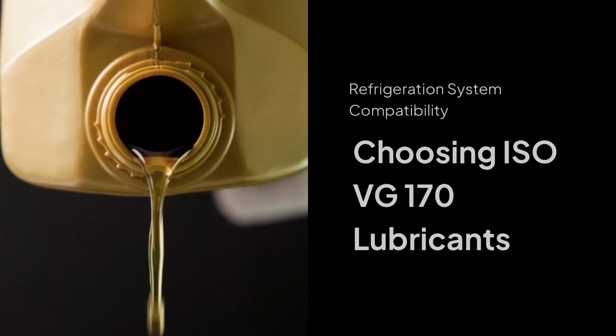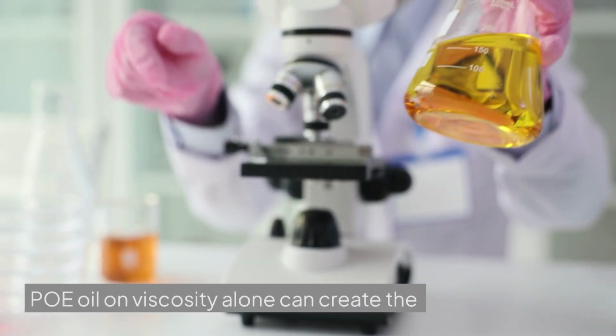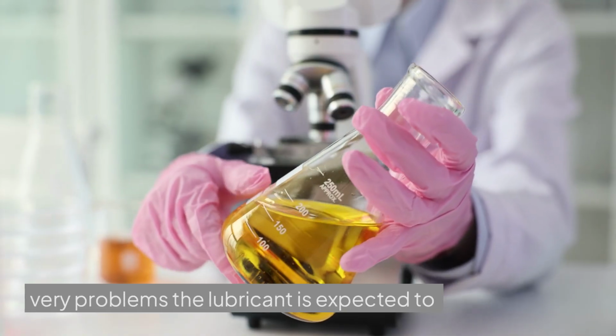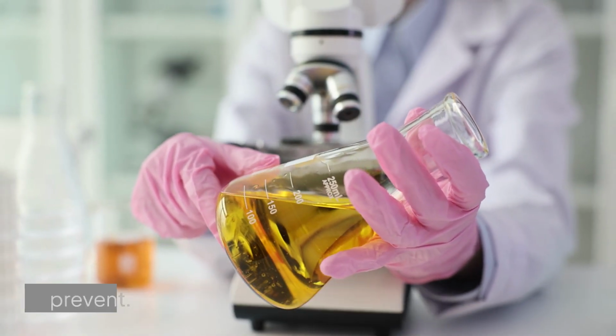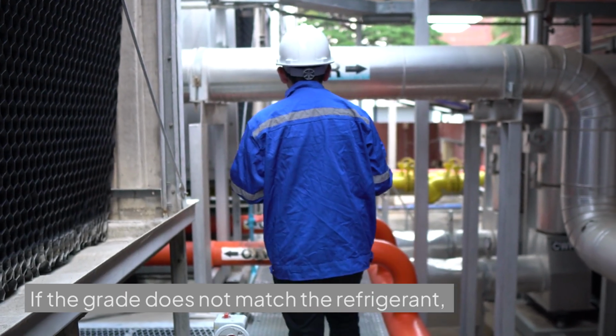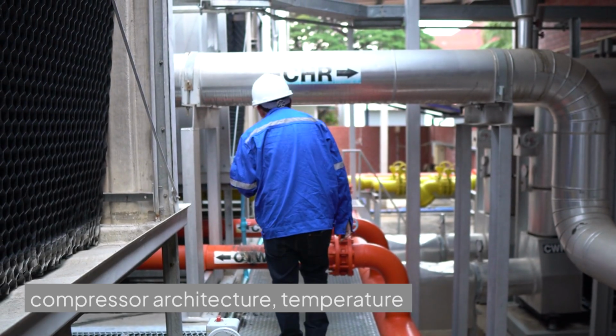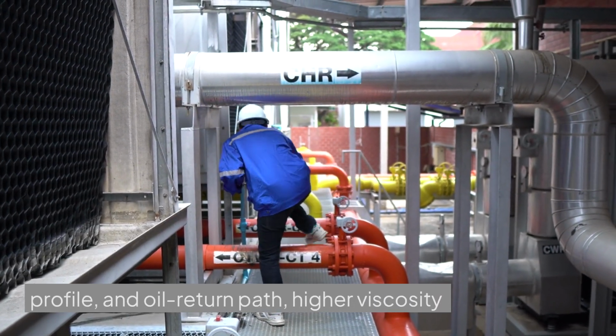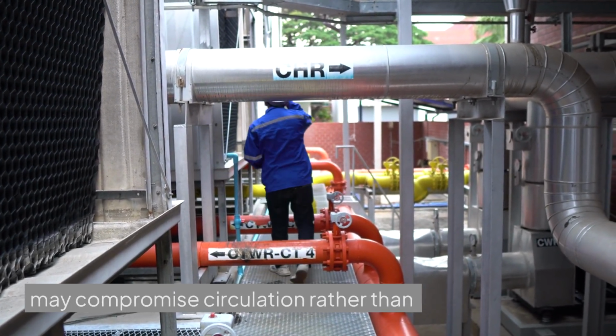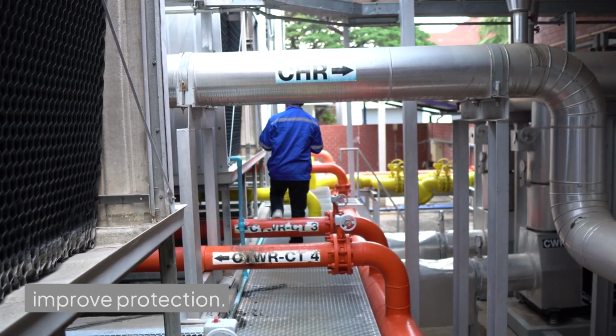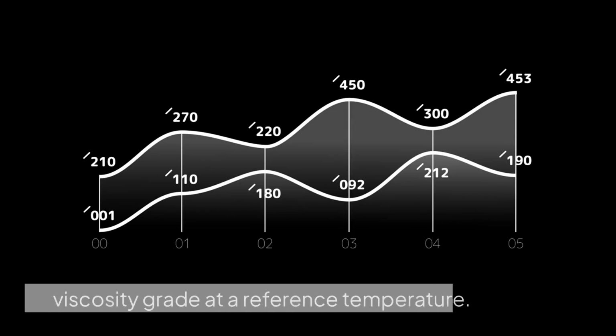Choosing ISO VG 170 POE oil on viscosity alone can create the very problems the lubricant is expected to prevent. If the grade does not match the refrigerant, compressor architecture, temperature profile, and oil return path, higher viscosity may compromise circulation rather than improve protection. ISO VG 170 identifies a nominal kinematic viscosity grade at a reference temperature.